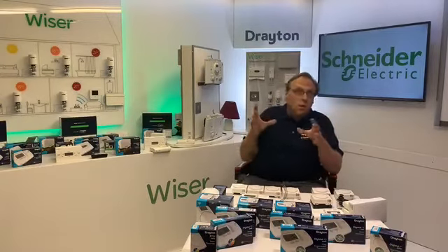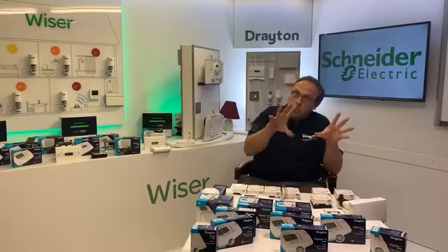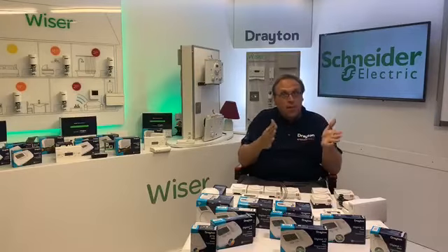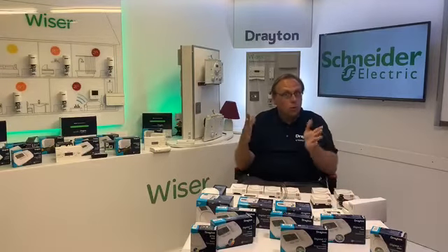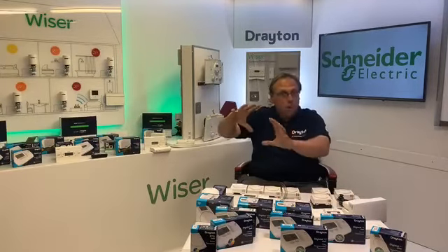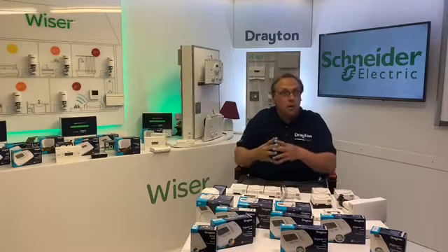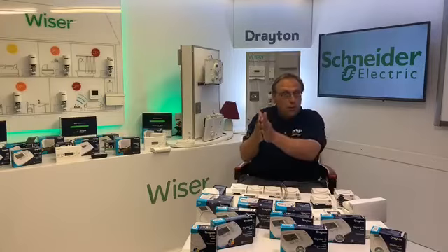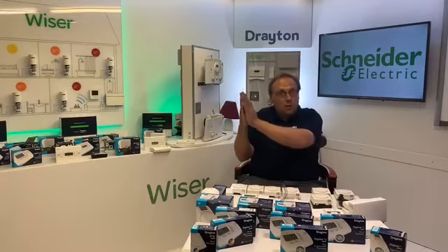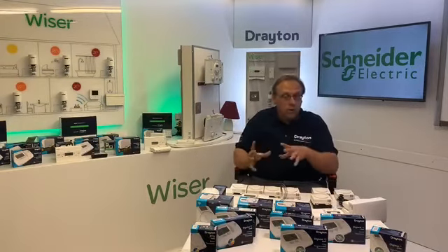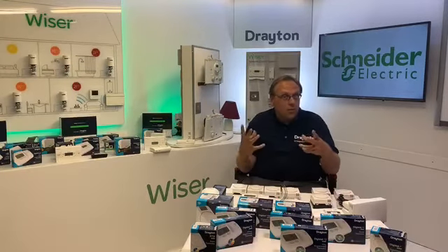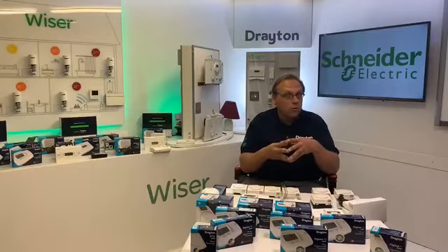If we think in terms of the whole system, it starts off with your timer, time control, either your programmer or your single channel timer. That then is essentially a switch which outputs to your temperature control, which is a switch activated by temperature. So we're sort of in the middle between time switch and either boiler or motorised valve. So that's what we're looking at today. That naturally branches into two sets of temperature controls. We've got central heating and we've also got the hot water.